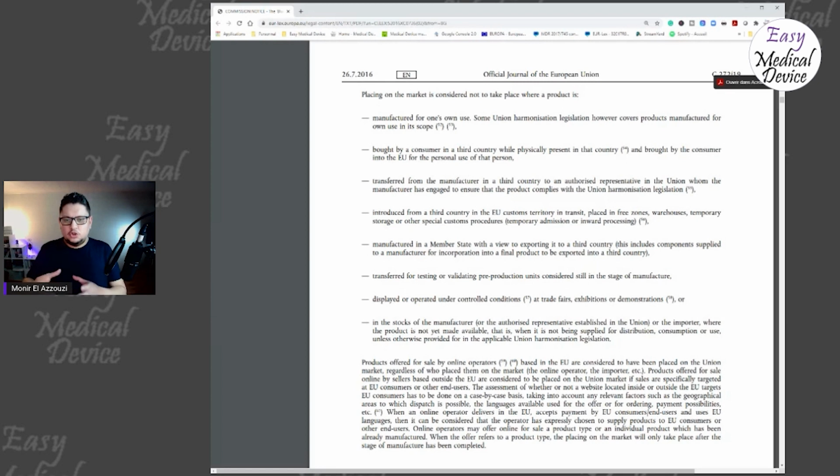If, for example during the transition period, you identify a change that seems really significant, because you understand what significant changes are, the EU MDR mentions it specifically. If the change is significant and you confirm that it's not compliant, you have the right to stop distributing the product. Actually, it's not only the right, you have to stop distributing the product.